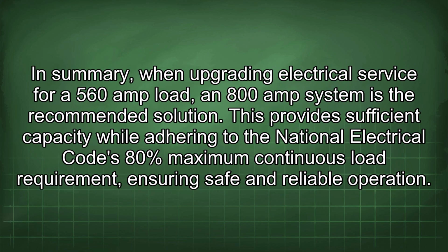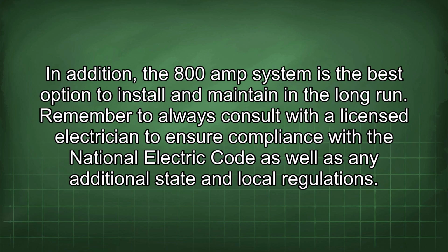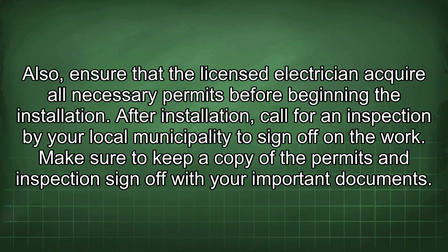In summary, when upgrading electrical service for a 560 amp load, an 800 amp system is the recommended solution. This provides sufficient capacity while adhering to the National Electrical Code's 80% maximum continuous load requirement, ensuring safe and reliable operation. In addition, the 800 amp system is the best option to install and maintain in the long run. Remember to always consult with a licensed electrician to ensure compliance with the National Electrical Code as well as any additional state and local regulations. Also, ensure that the licensed electrician acquires all necessary permits before beginning the installation.